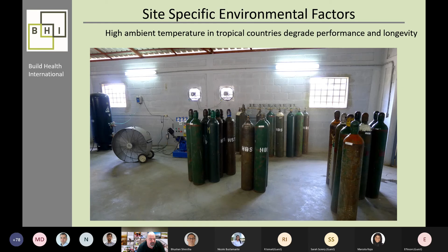Another important factor that's overlooked is altitude. When you get into countries like Kenya, where you can have hospitals at altitude of 6,000 or 7,000 feet easily, you have to understand that the generator and the components of that generator have to be sized for that altitude. Really over 300 meters, 1,000 feet, you have to start adjusting the size. So a plant at 7,000 feet, we're working on plants in Kijabe, Kenya, which is that elevation, you're losing 30% of your compressor output, and that has to be compensated for.